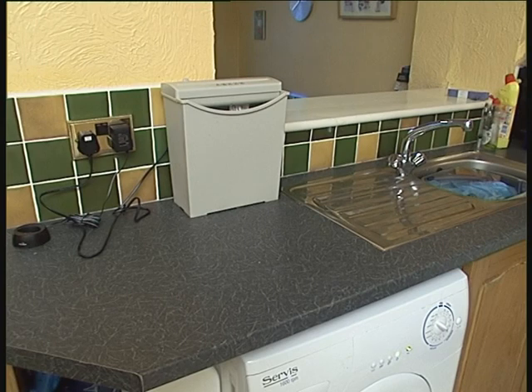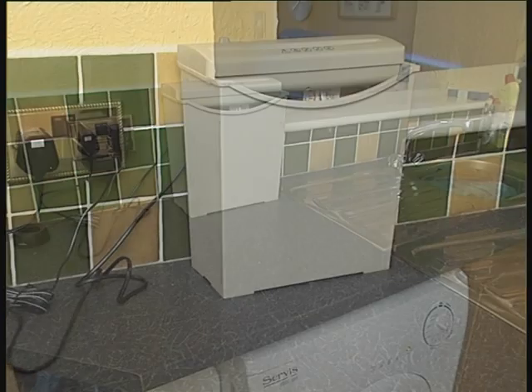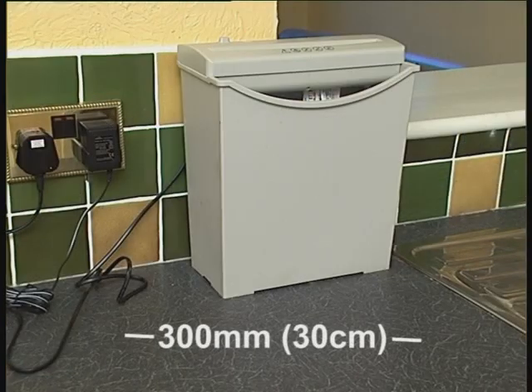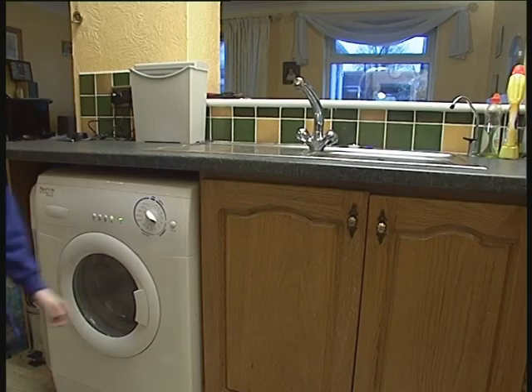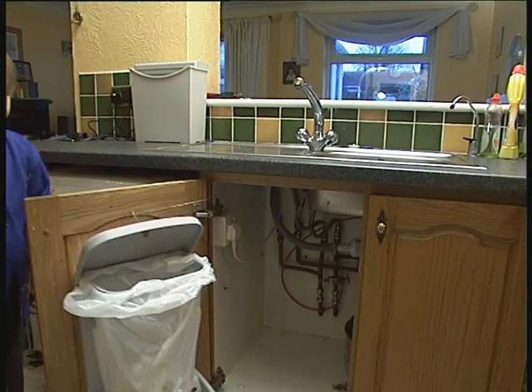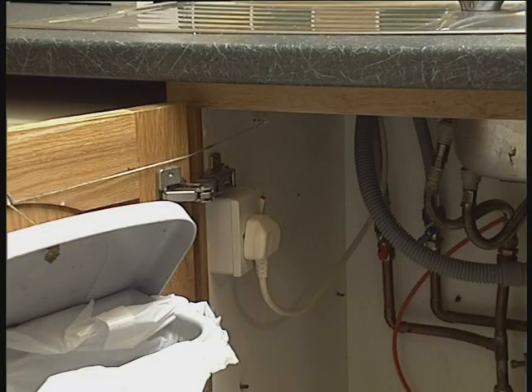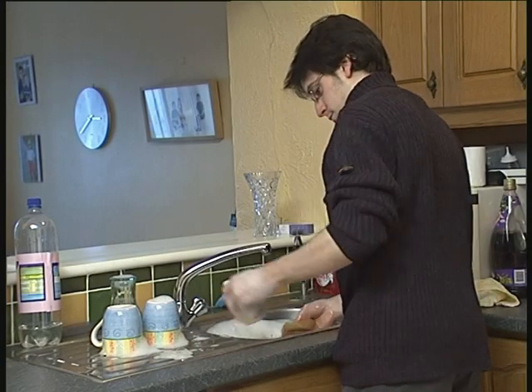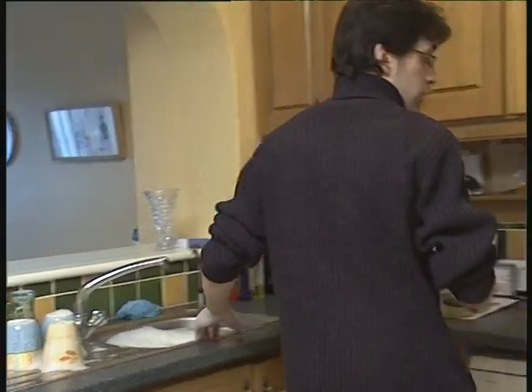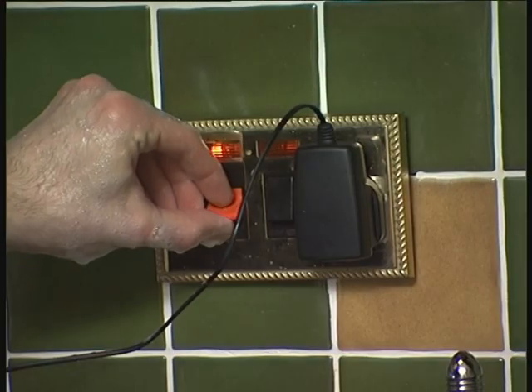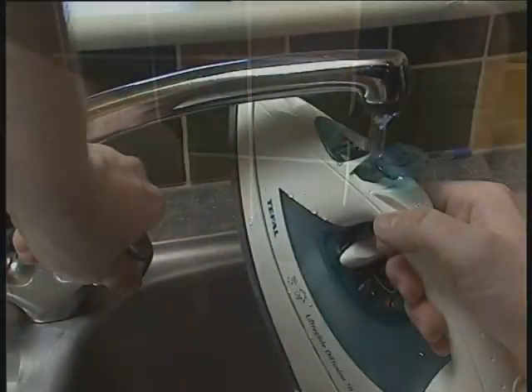But here, because people are unlikely to be wet through, the recommended distance between sockets and the sink is at least 300 millimetres. This situation, where an extra socket outlet has been provided under the sink to power the washing machine, could be a potential cause of electric shock if there was a water leak. As a general rule of thumb, don't operate any electrical switches or appliances with wet hands. Don't clean or fill kettles or irons while they're still plugged in.